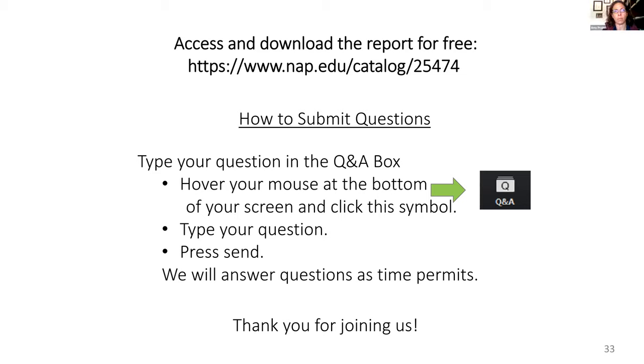Right, that's correct. The report cites field studies where the secondary disinfectant residual was switched to chloramines and numbers of Legionella decreased, also at the building scale when chloramine disinfection units are installed. And we bring to light that scientifically it's not known exactly why chloramine has these advantages, and it would be useful to know in terms of optimizing its use and application.